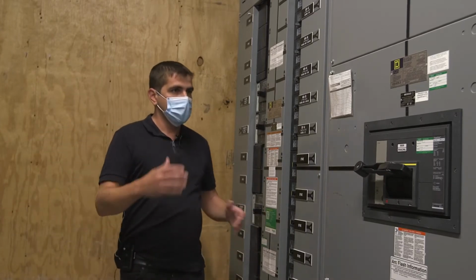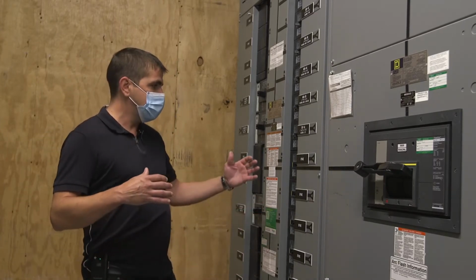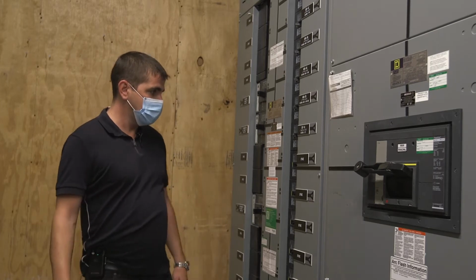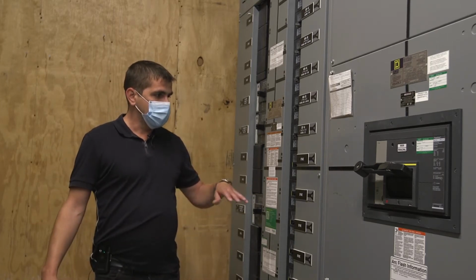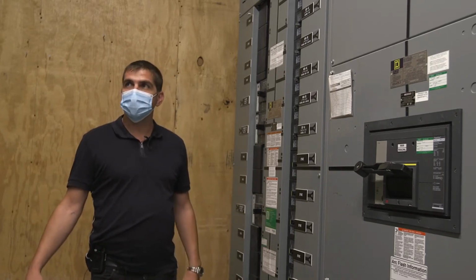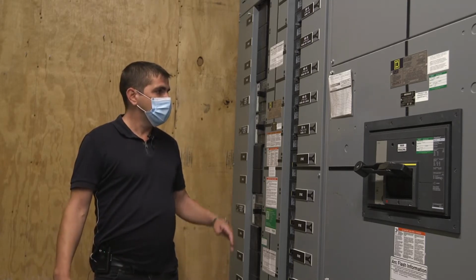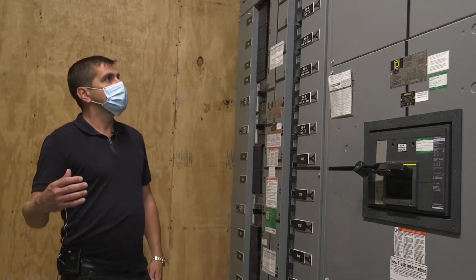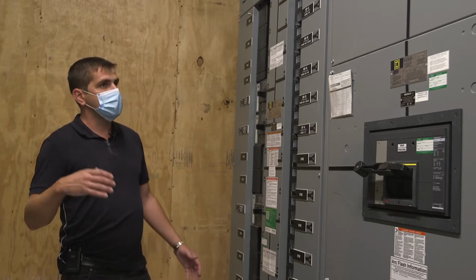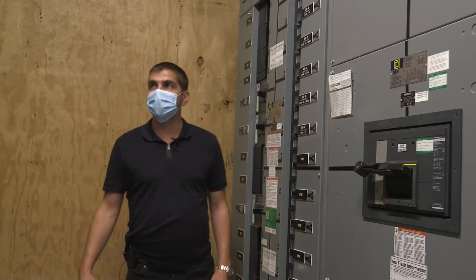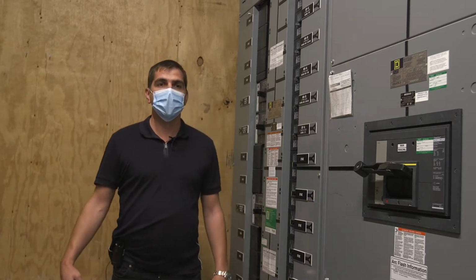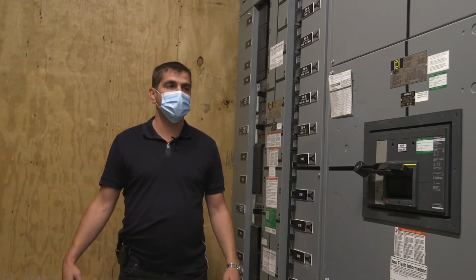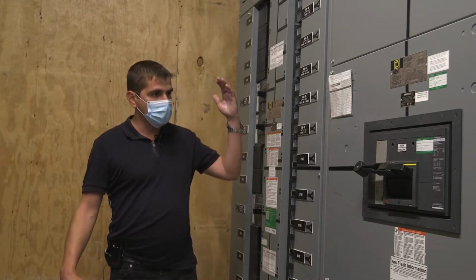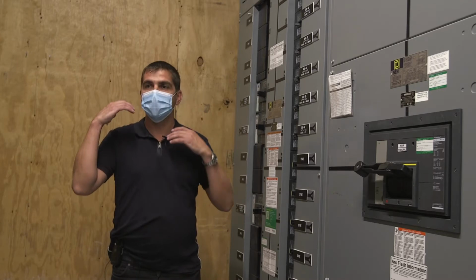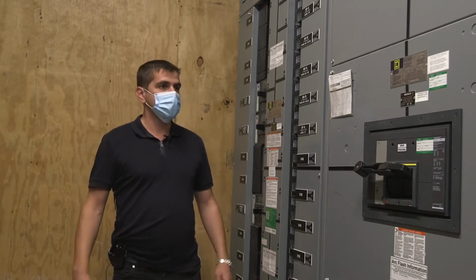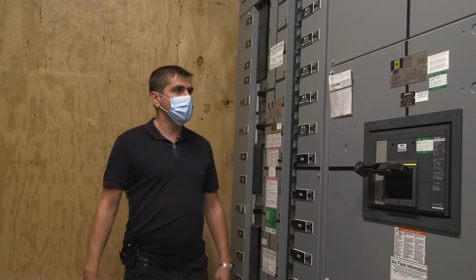Basically, the idea is that this equipment really doesn't require much maintenance. It's just, from time to time, making sure that the system operates properly. You would check all of the contacts and the temperature on the contacts. Most likely when something is about to fail, you have to verify that the contacts don't create additional heat because of improper contact.